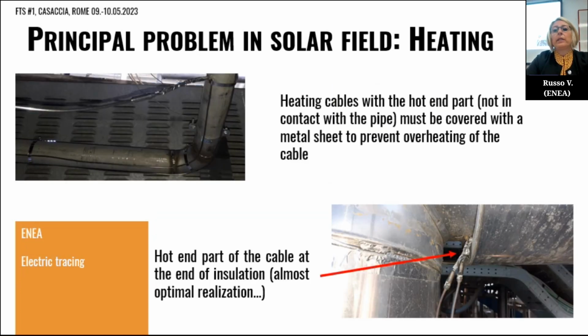Here we have another aspect to consider when installing the tracing cable: the correct position of the terminal part of the cable, the part not in contact with the pipe, but this part is hot. This hot part must be covered with a metal sheet in order to prevent overheating. Here we can see in this picture the cable covered by a metal sheet. And here we can see an almost optimal realization of the coverage of the end part of the cable that goes out from the insulation of the pipe.